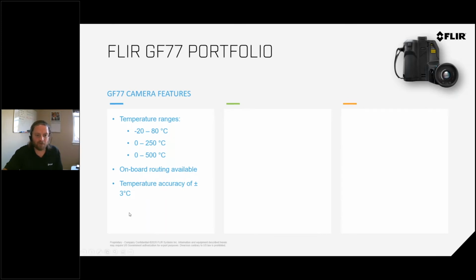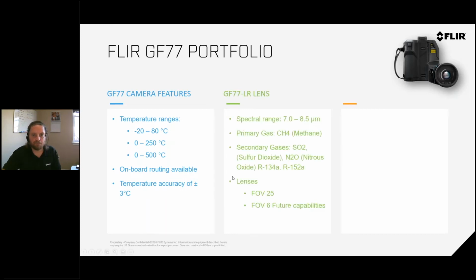And then temperature accuracy of this camera is plus or minus 3 degrees Celsius, which is pretty good for these applications. We've been selling a lot of cameras lately for elevated skin temperature, right? So if you're scanning a human and you have a plus or minus 3 degrees Celsius, that's way too big for scanning a person to see if they have a fever or not. But to see if you have a connection that's too hot or a fuse panel that's too hot, you're going to see that heat anomaly. It's going to be plenty accurate for those applications.